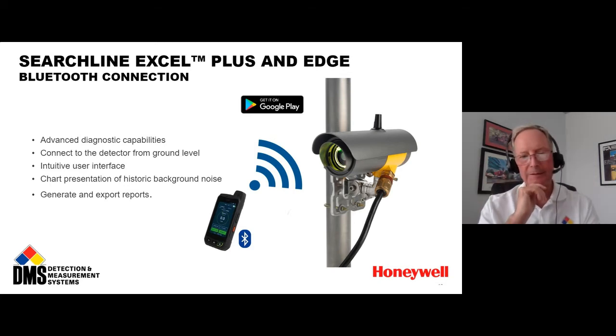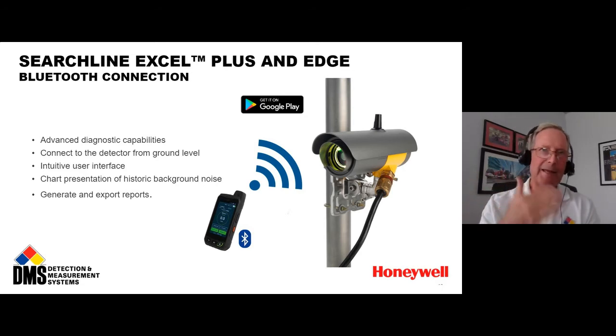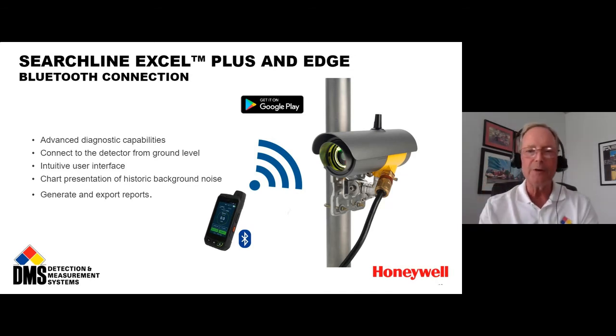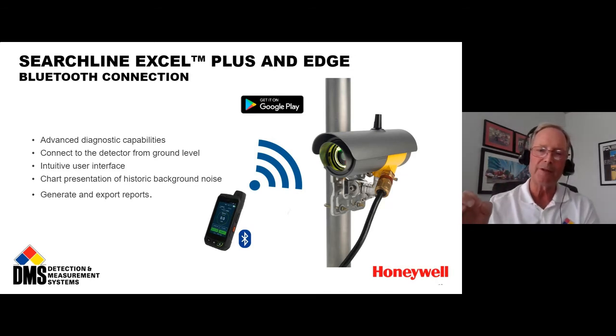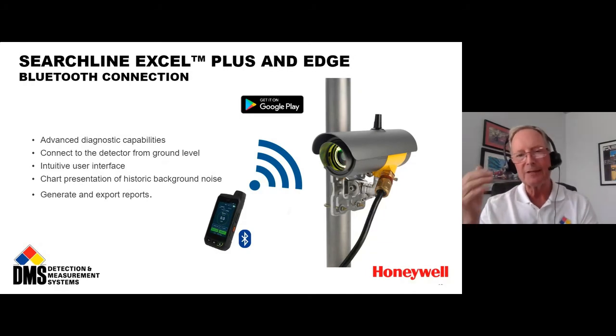But what you can do with these things is so amazing, because from the commissioning process, setting up the alignment, confirming the alignment is correct, testing the detector with test filters, all of that is a step-by-step process the app walks you through one step at a time. After each step it confirms proper operation from the detector and tells you what the next step is. It is absolutely idiot proof.